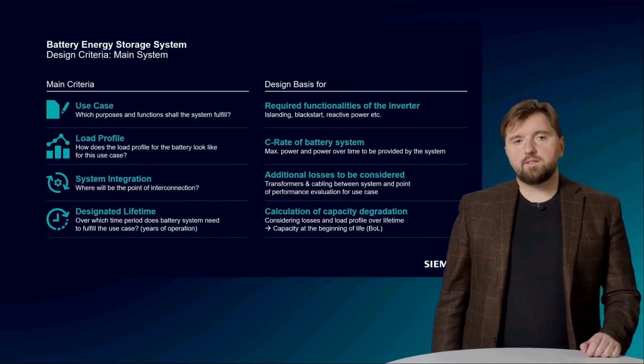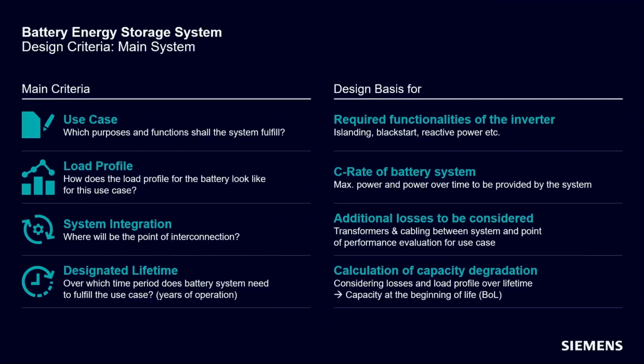Let's talk about BESS design criteria. When designing a BESS, several key factors must be carefully considered to ensure optimal performance and length of life. First and foremost, we must define the use case. What purposes and functions will the BESS serve? Will it be for peak shaving, frequency regulation, or something else? This will directly provide us with the required functionalities of the inverter, like whether we need islanding, black start, or reactive power capabilities. Next, we need to analyze the expected charging-discharging profile of the BESS.